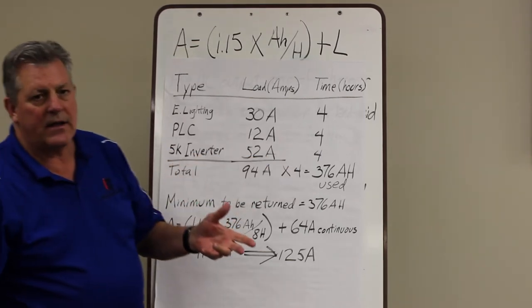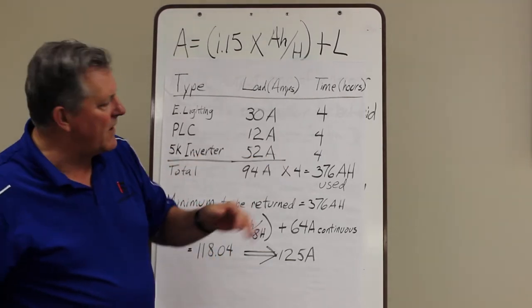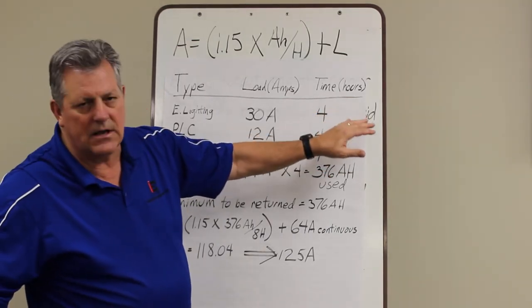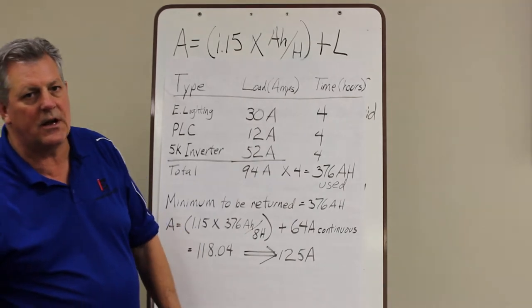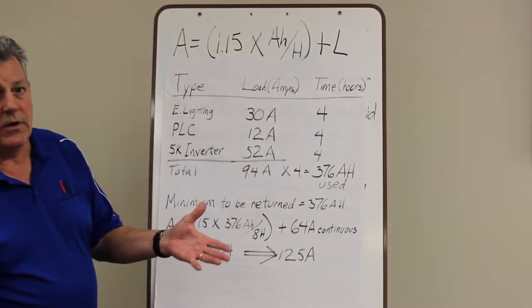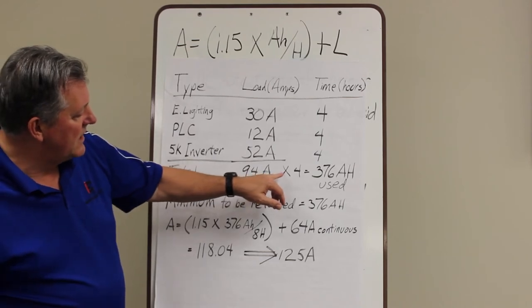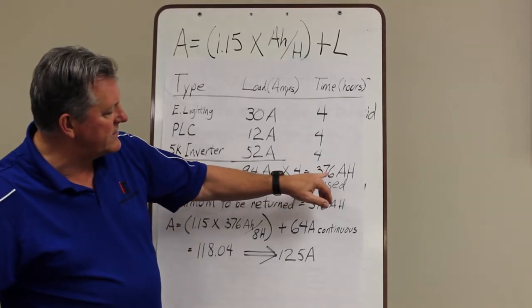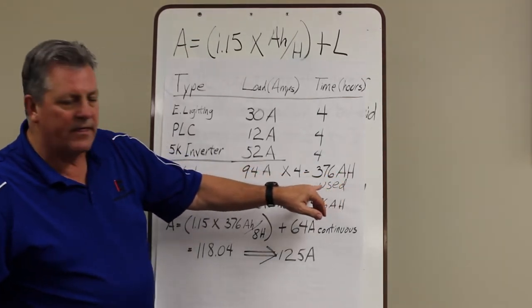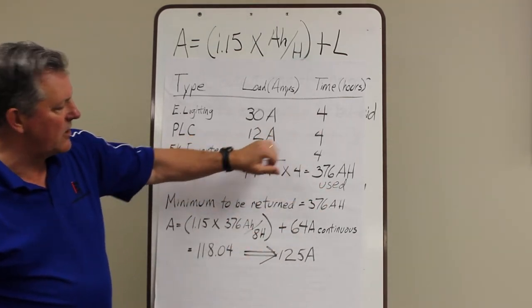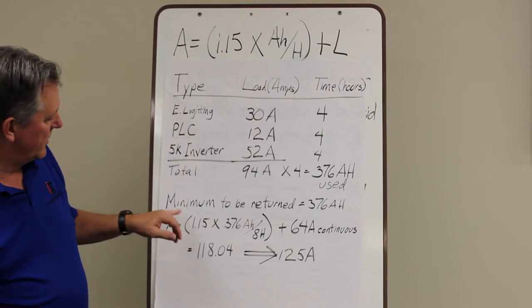Now if you go back and you're trying to size the battery you might have to look at this or if it's a step load profile you'd have to look at this in minutes. We're going to get through this thing quickly. So the total is 94 amps for 4 hours which is 376 amp hours. That's the amount of amp hours used to keep this load running for 4 hours. Pretty simple.